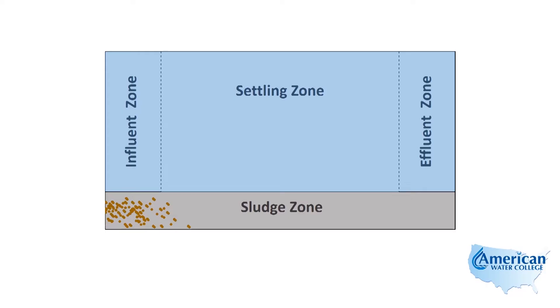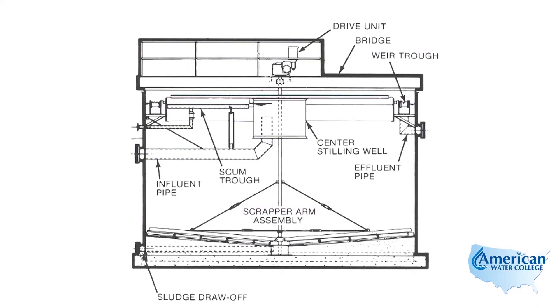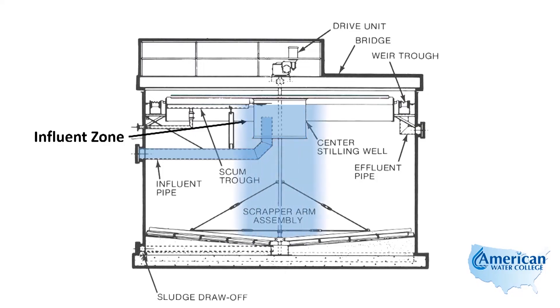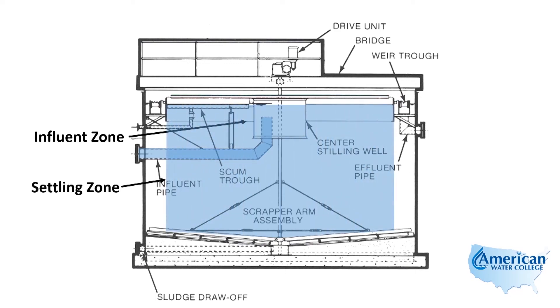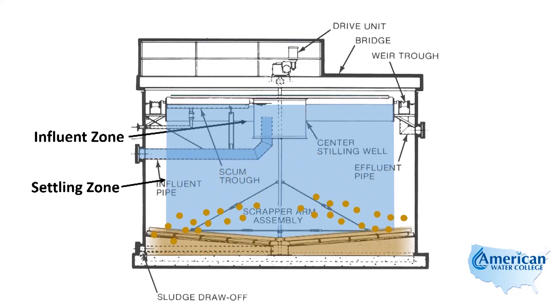Here we have pictured a round clarifier, or circular clarifier. The water comes in through the influent into the center stilling well — this is the influent zone. The water then leaves the stilling well and moves outward through the settling zone as the settleable particles settle out and enter the sludge zone down at the bottom of the clarifier.